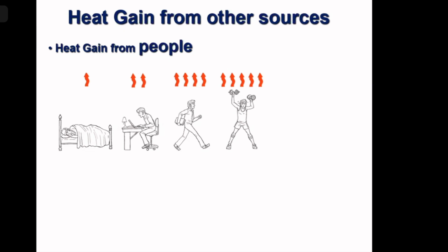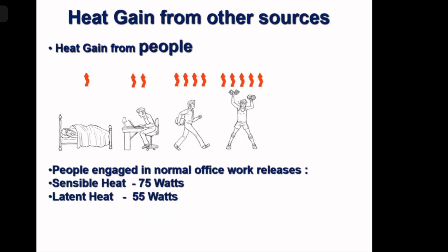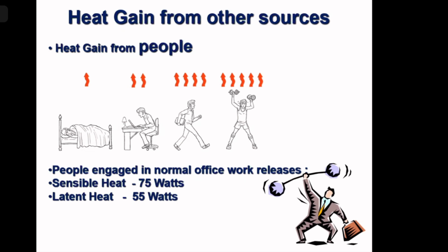Now, there is heat gain from other sources. Heat gain from people. You see, if you are sleeping, you are releasing less heat. If you are working on a table, you are releasing a little more heat. If you are moving and doing exercise in a gym, you are releasing even more heat. So people engaged in normal office work release sensible heat of 75 watts and latent heat of 55 watts. We can consider it for our calculation. Each person, 75 watts sensible heat and 55 watts latent heat. If there are 10 people, we should multiply it by 10. Unless your boss makes you work like this in an office, we consider 75 and 55. But if your boss makes you work like this, of course, the heat released by you will be more.